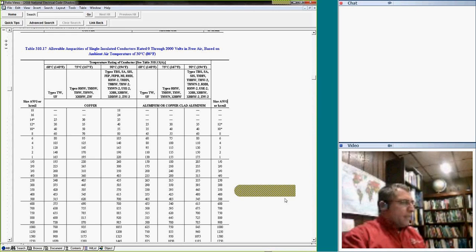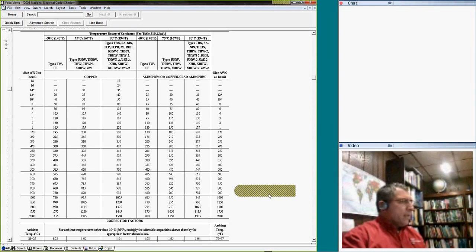Let's look at the 500 kcm, the same thing. I like the 500 kcm, guys. Suppose I have my 500 kcm conductor in the air, and I have my insulation, here's my 75, 90, 75. If I put it in the air, look how much current I can get out of my THHN conductor. Or in case I don't have THHN, because it's in the air, it's THHW, outside. I carry 620 amps. That is almost double the amps I can carry out of 500 kcm if I put it outside on a pole.